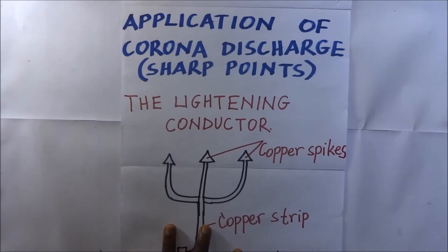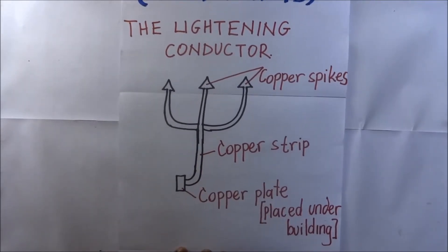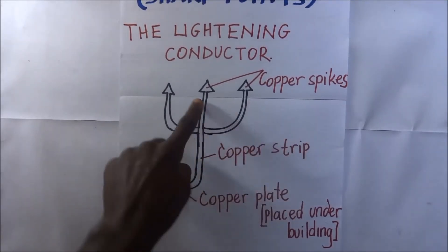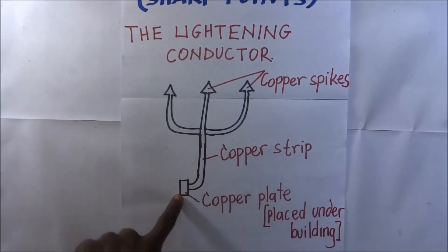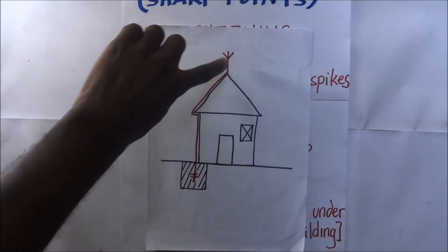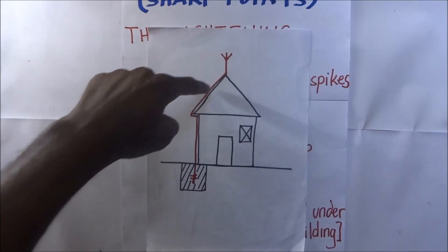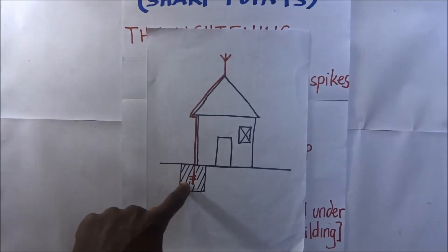So now when all this happens, how does the lightning conductor work? Here we have a schematic diagram of a lightning conductor. In this diagram, we have copper spikes that are connected to a copper strip, and at the bottom is a copper plate. The lightning conductor with its copper spikes is connected to a copper rod which goes along the building and is buried into the ground.